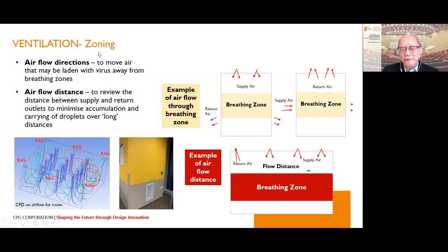An interesting point is zoning. The air is supplied at the top, at the roof, not at the ceiling of the room. The supply air is exhausted and returned back to the air handling unit at low level. In this way, the air sweeps through the breathing zone, and the accumulation of virus pollutants is reduced in the breathing zone.